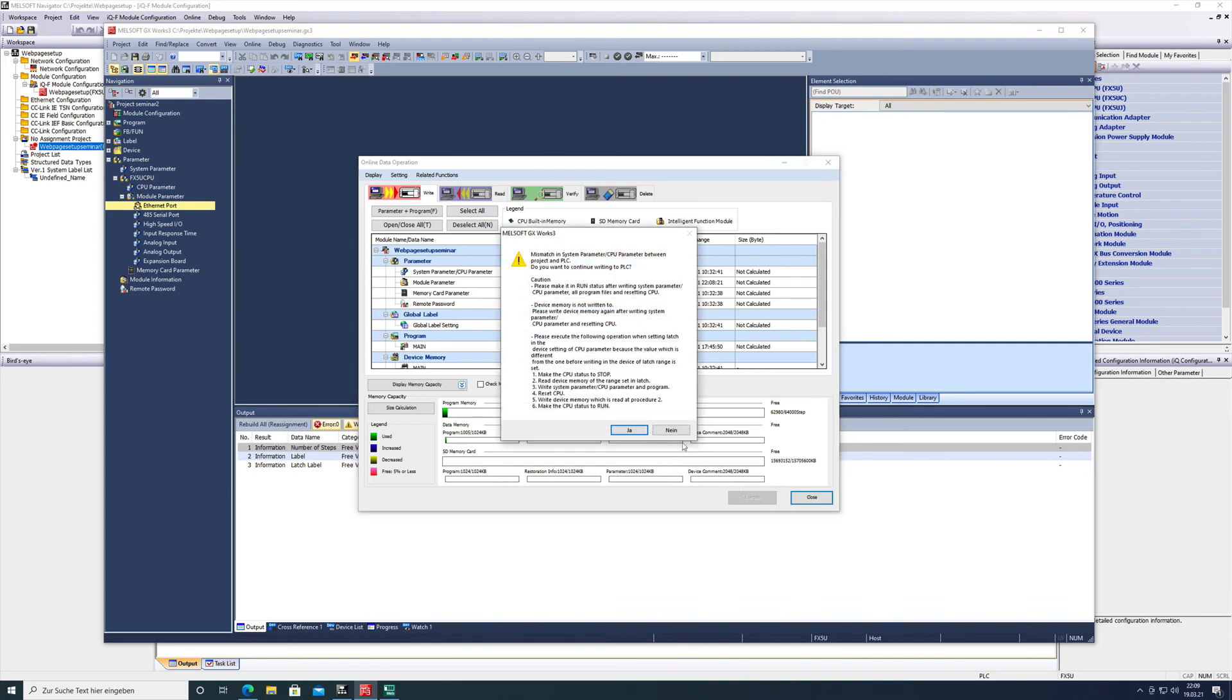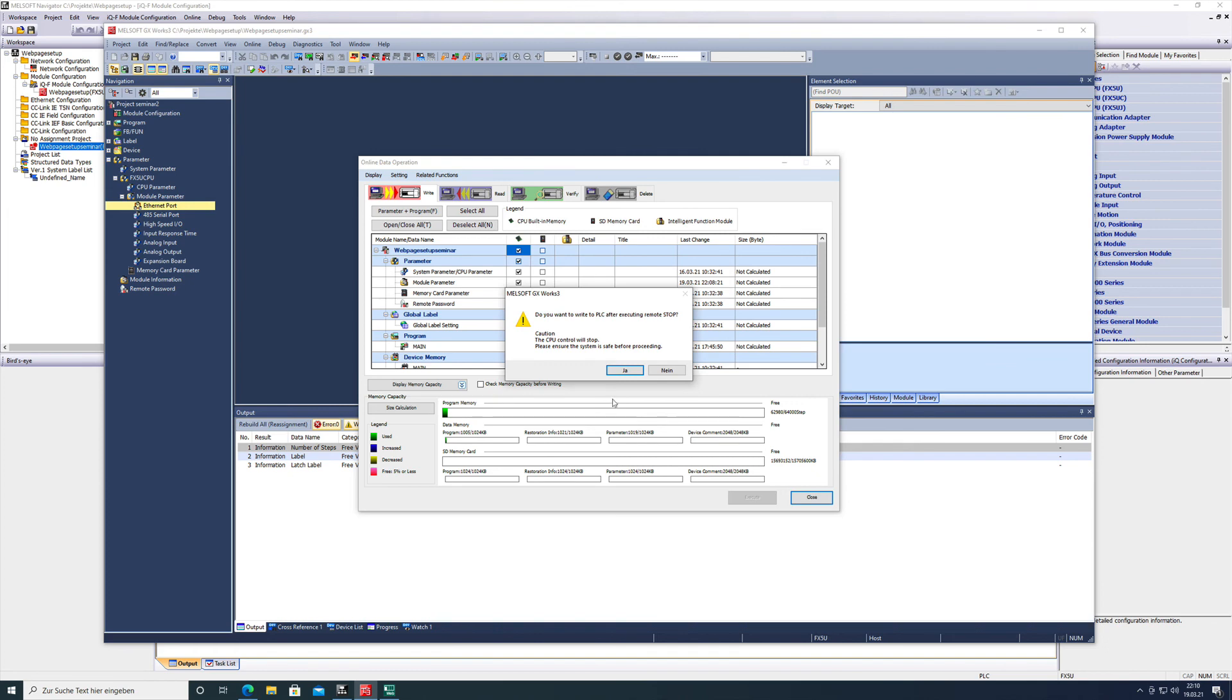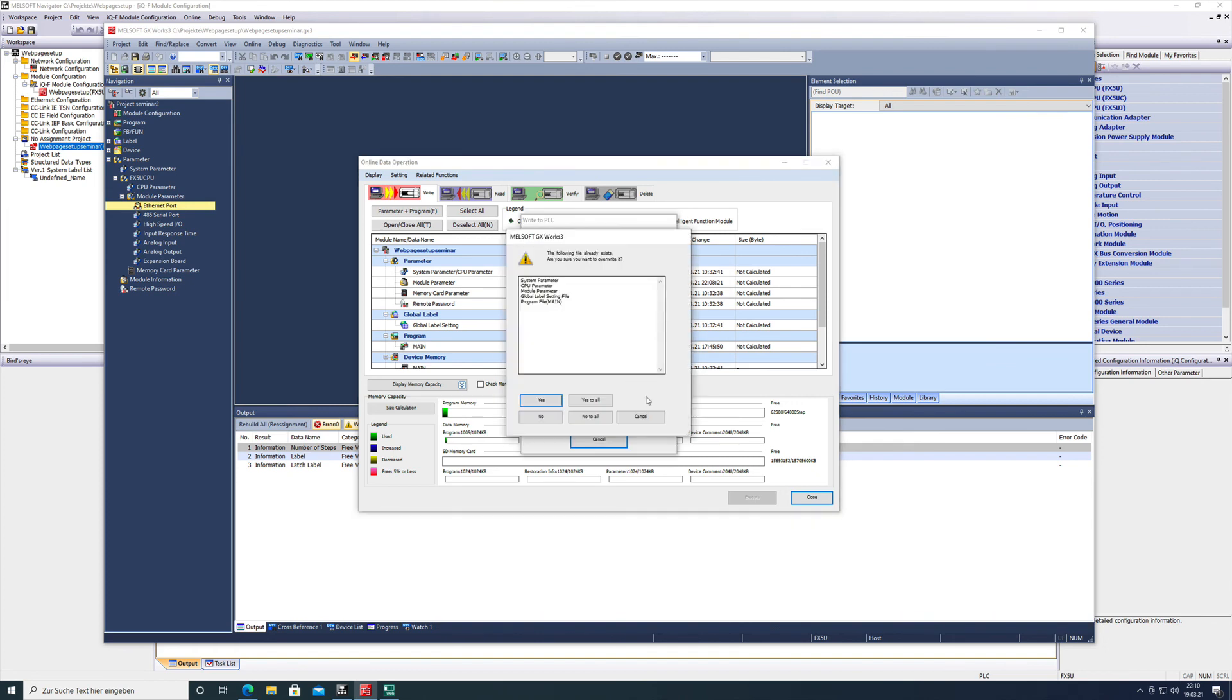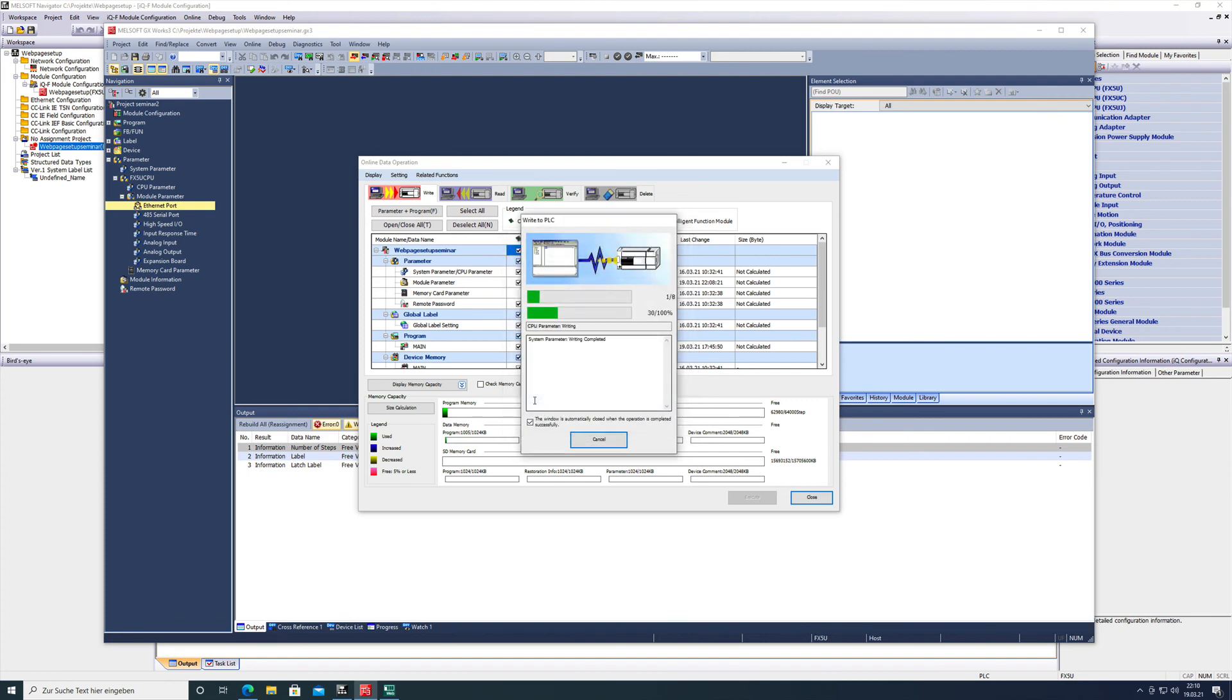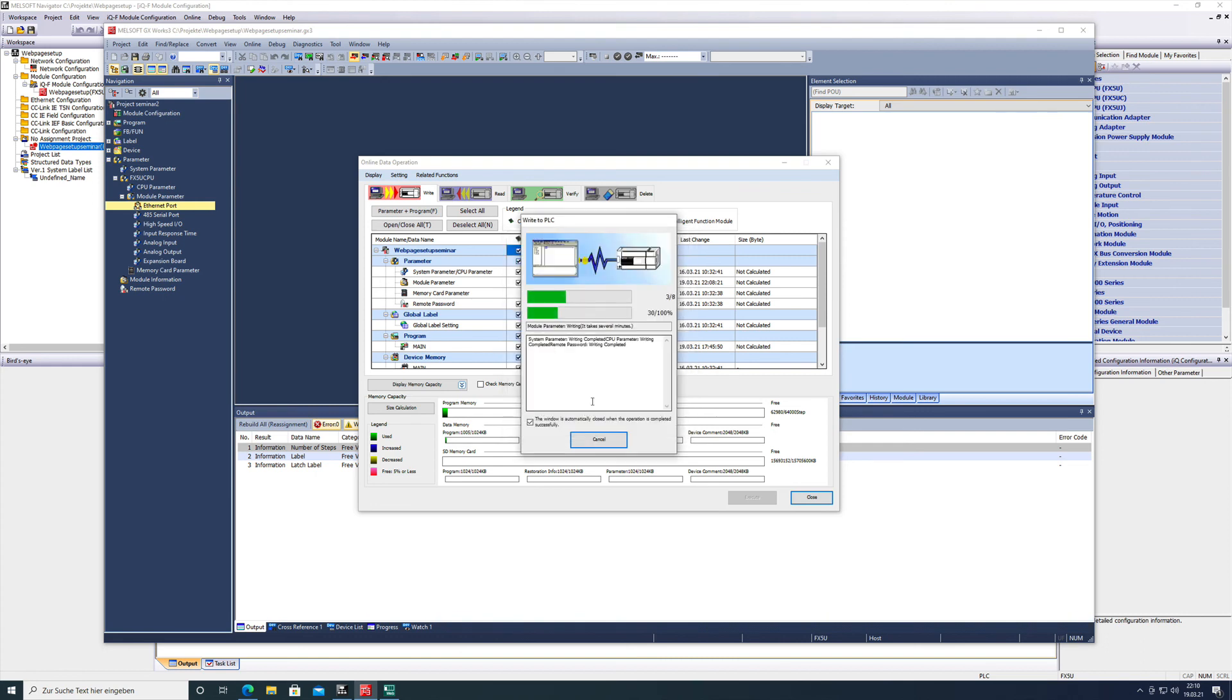When this window shows up with all the messages, you can go through and read them. The first thing is a mismatch in system parameters, which is normal because you don't have any parameters in the CPU anyways. You can just read all the other messages and go ahead and confirm the settings. The download should start any second after the CPU is in stop, and then confirm it again. The remote password also has to be confirmed.